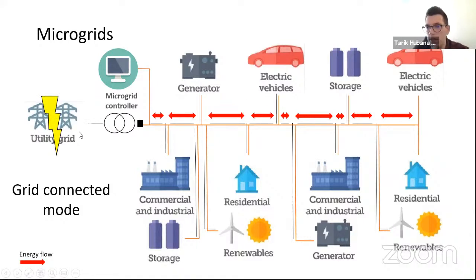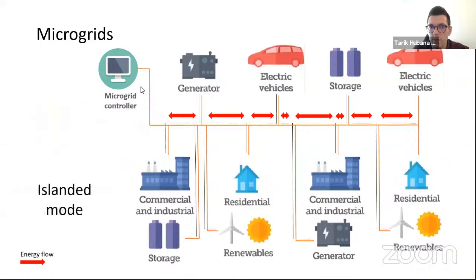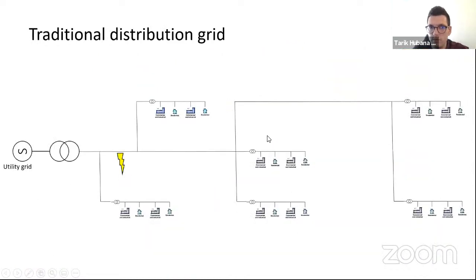So this means that if a fault occurs at the primary utility grid, this microgrid can go totally into islanded mode and be resilient and have energy supplied to its local consumers. So what does it mean? We can see here on this slide where we have the utility grid and a couple of microgrids that are connected in a radial manner, which is common in distribution systems.